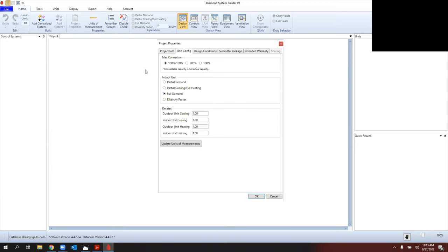For indoor unit, always select residential equipment at Full Demand. Full Demand means everything running at your design temperatures — what you'll get out of each zone with all indoor units running. There are other options for VRF or partial demand, but for residential applications keep it on Full Demand since we select equipment at full demand at design temps. The system will start to adjust as we build it — Derates start at 1.0 on auto pre-fill, so don't adjust those.